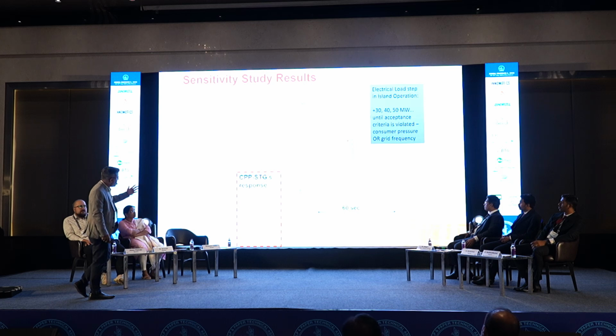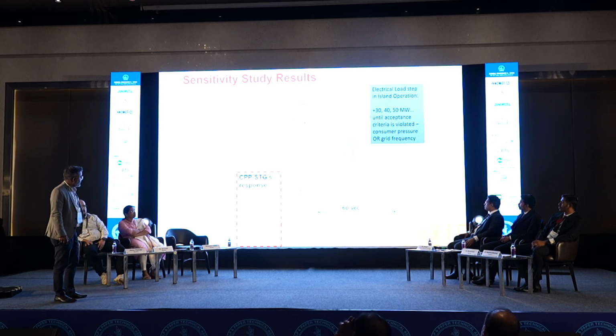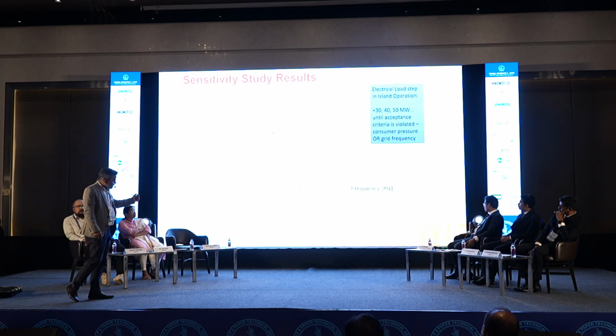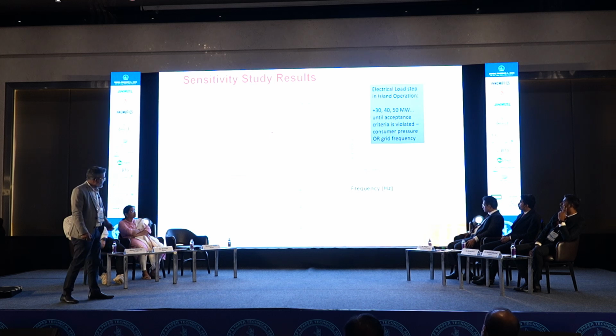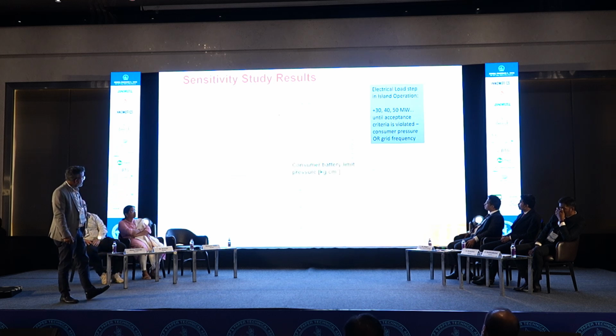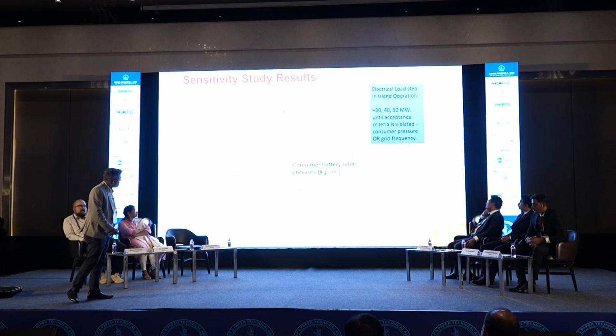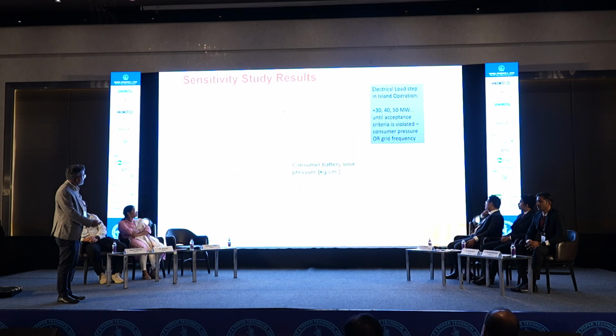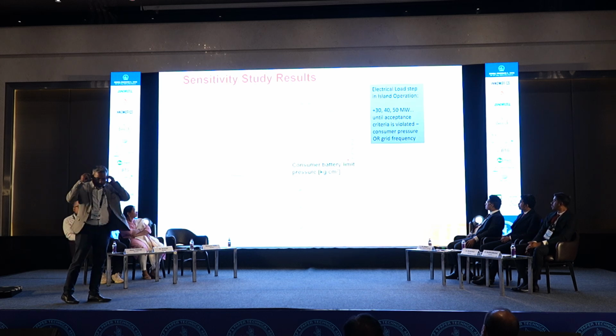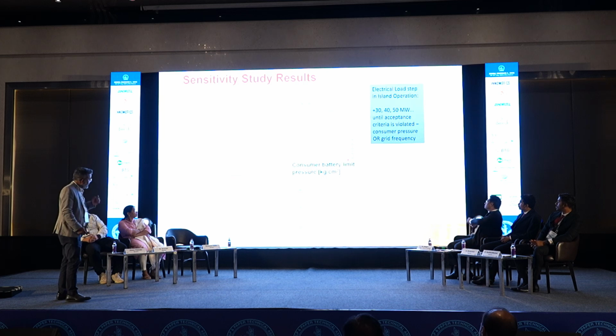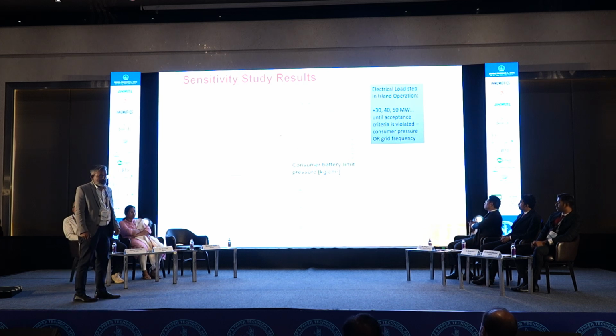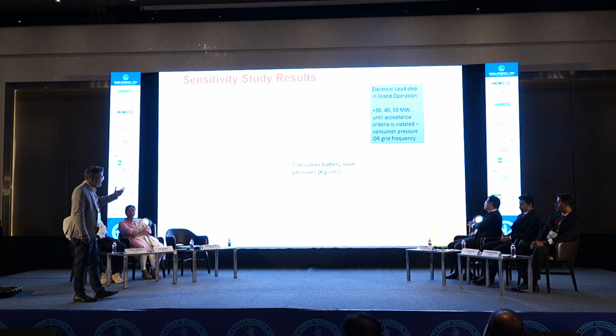And we also saw how the STG responses are, which are quite fast in action, within 60 seconds they are getting stabilized. The frequency in an islanded mode for each load step is well within the protection limits or allowable limits. The consumer battery limits are also quite important to see, because for the 70 megawatt load step, the purple trend, if you see, their PTA 3 plant will trip if the pressure goes below this acceptable range. So we cannot go below this step, or the plant cannot survive in this condition, otherwise PTA 3 will get tripped.